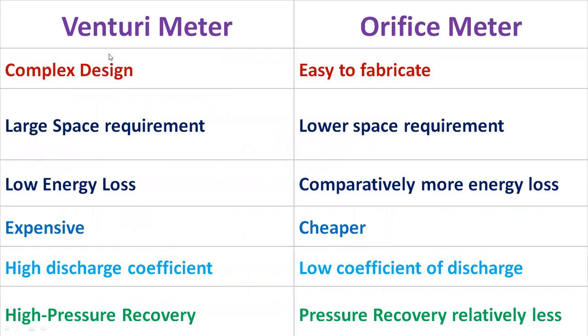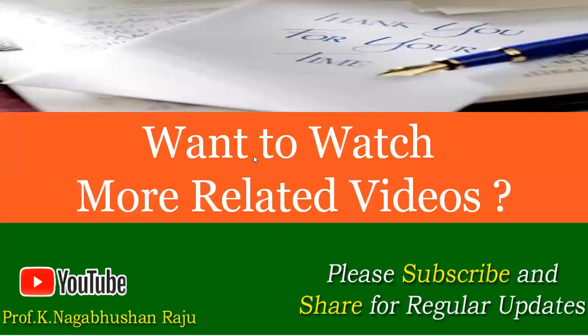In comparing the venturimeter and orifice meter: the venturimeter is complex in design while the orifice meter is easy to fabricate; the venturimeter requires large space while the orifice meter requires less space; the venturimeter has low energy loss while the orifice meter has comparatively more energy loss; the venturimeter is expensive while the orifice meter is very cheap; the venturimeter has a high coefficient of discharge while the orifice meter has a low coefficient; and the venturimeter has high pressure recovery while the orifice meter has relatively less. Thank you for your time. Hope you have enjoyed the session.